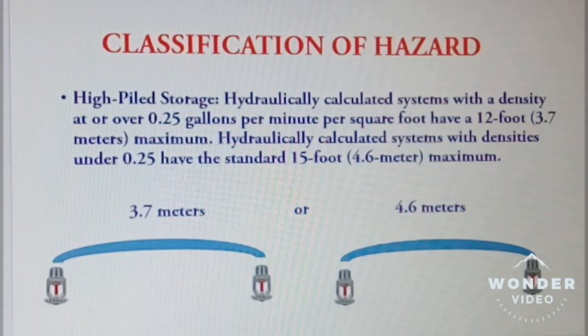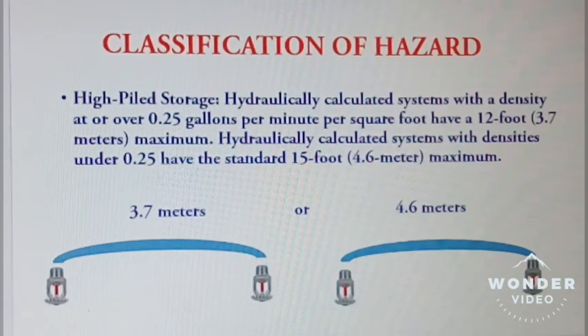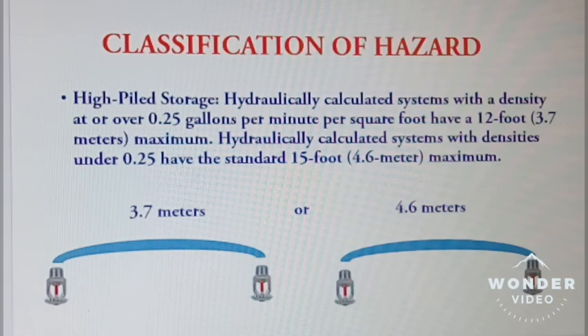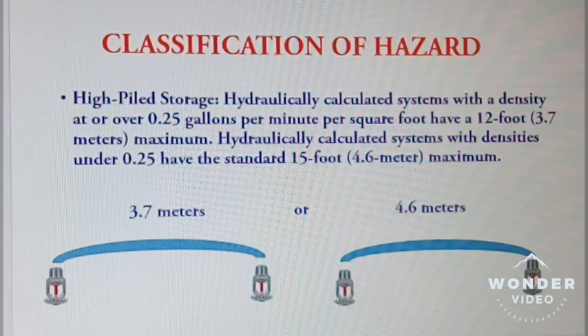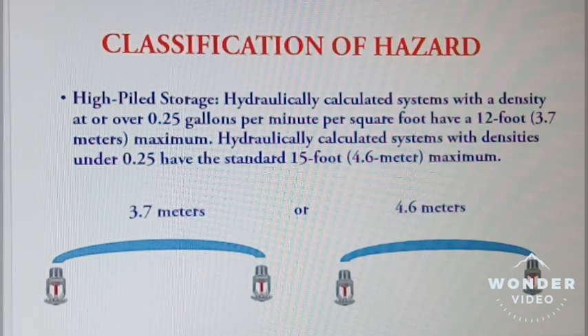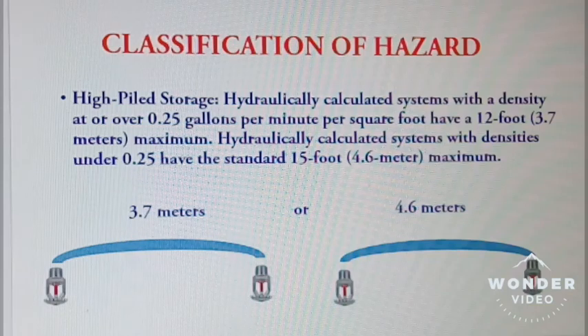High-piled storage: hydraulically calculated systems with a density at or over 0.25 gallons per minute per square foot have a 12 foot, equivalent to 3.7 meters, maximum spacing. Hydraulically calculated systems with densities under 0.25 have the standard 15 feet, equivalent to 4.6 meters, of maximum spacing between them.